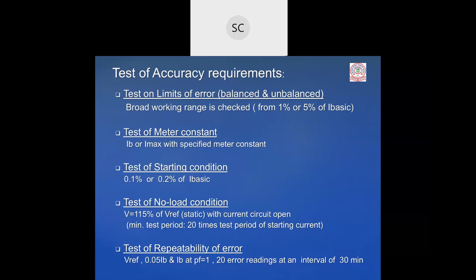The difference between maximum and minimum depends upon the accuracy class. It is 0.7 or 1.5. If it is class 2, it is 1.5. It is 0.7 in case of class 1 accuracy. So it has to be maintained. So the test of repeatability of error is required. That means they all fall within some plus or minus limit. It will not go beyond that.